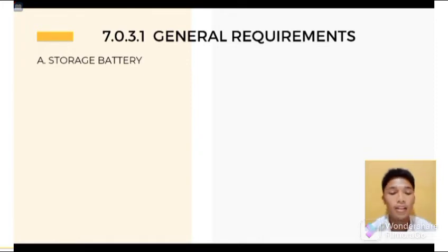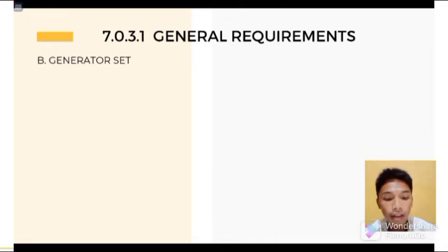Okay, so we need to take note of this, that automotive type batteries shall not be used as a storage battery for the sources of power. An automatic battery charging means shall be provided. Next, generator set. Generator set as a source of power. First is the prime mover driven.